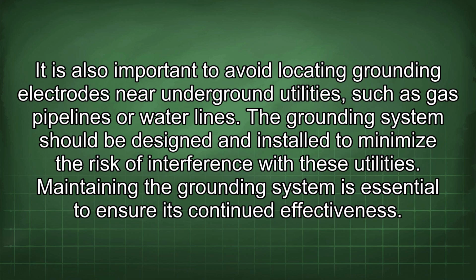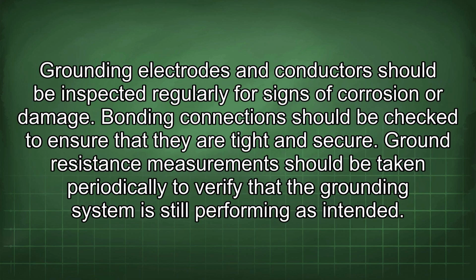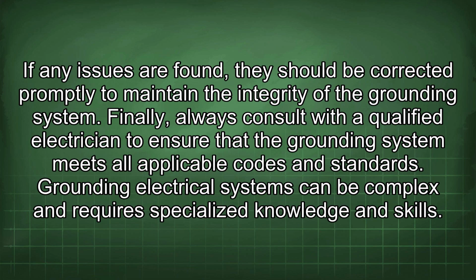Maintaining the grounding system is essential to ensure its continued effectiveness. Grounding electrodes and conductors should be inspected regularly for signs of corrosion or damage. Bonding connections should be checked to ensure that they are tight and secure. Ground resistance measurements should be taken periodically to verify that the grounding system is still performing as intended. If any issues are found, they should be corrected promptly to maintain the integrity of the grounding system.